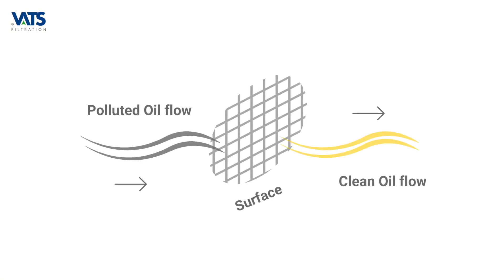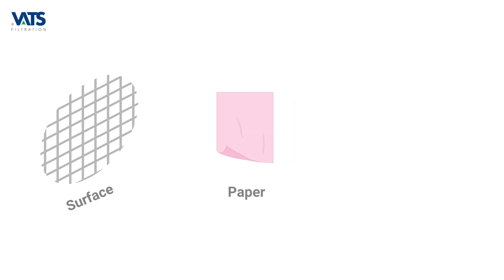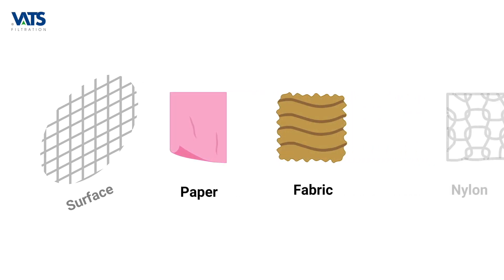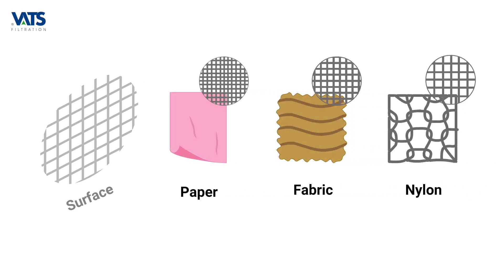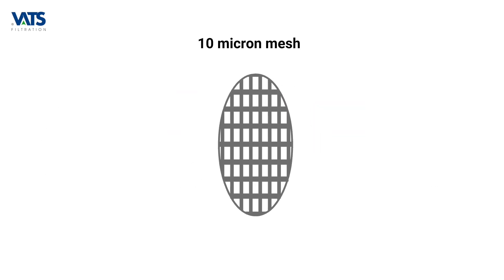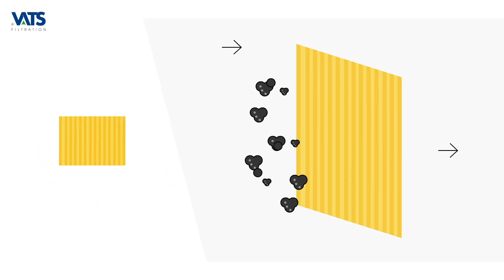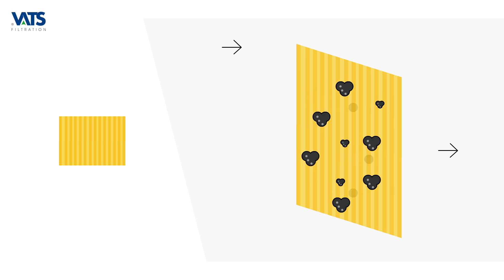The simplest way to begin understanding the filtration process is to visualize a simple surface filter — just a sheet of paper, fabric, or nylon. The mesh size of the sheet will decide the particle size removal threshold. So if you use a 10-micron mesh size, particles above 10 microns will be retained and particles smaller than this will pass through.